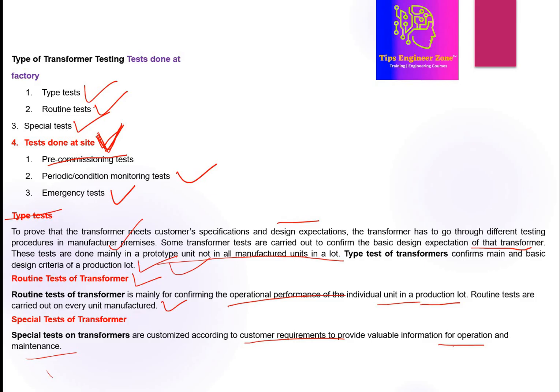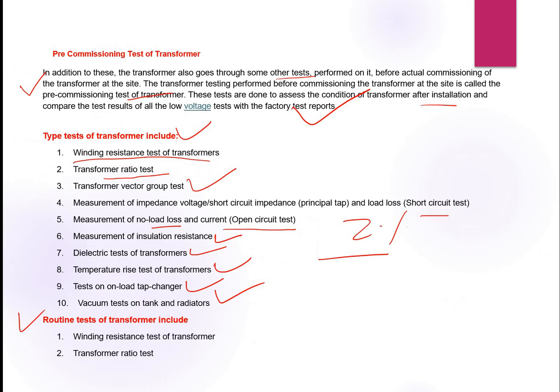And the fourth is the tests done at the site, meaning pre-commissioning tests, emergency tests, and periodic tests. Type tests are generally performed only on selected units, routine tests are performed on all manufactured units, and special tests are sometimes a customized requirement. And pre-commissioning tests are also performed at the site. These are all the low voltage tests.